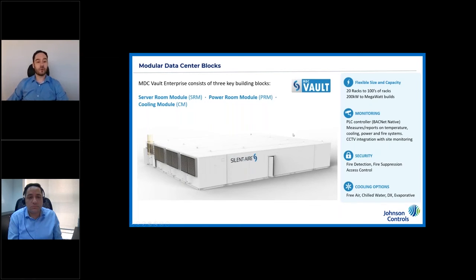The second component of any MDC, one of the critical items, would be your power rooms and the power room modules in our case. In this design shown on screen, our power rooms form part of the structure itself. In general this would include your switchgear, UPSs, battery backup, and we have a variety of different flavors of these power rooms and how they could meet the local jurisdiction's requirements for safety and life safety.